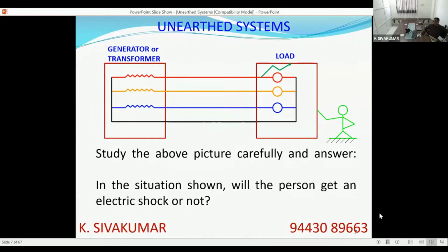Generally speaking, there will not be any closed circuit here, because the person is standing on earth but the neutral is not connected to earth. So there is no closed circuit. For a basic understanding, there will not be current flow through the human body, even in this condition. Leave alone the high-end complicated subject of capacitive coupling; we will come to that later. To start with, since there is no closed circuit, there will not be any current flow, even in the case of a single phase to ground fault. We will come to the intricacies later. Shock is a matter of current flow through the human body. So let us understand at present that since there is no closed circuit in this system, even though voltage is prevailing, there will not be current flow through the human body, and there will not be any shock.